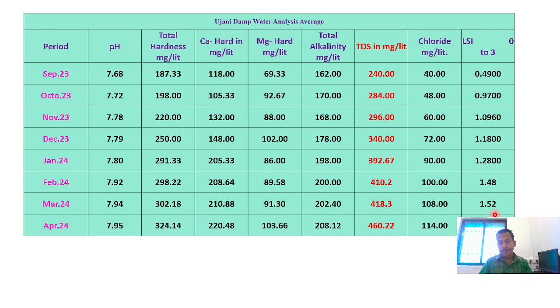That table clearly shows that in the month of September, the TDS was 240 for the Ujani Dam water and the LSI was 0.49, and in April the TDS is 460. That means it almost doubled, and similarly LSI increased up to 2, which is close to the higher limit, because the ASTM standard method sets the Langelier saturation limit at 0 to 3.